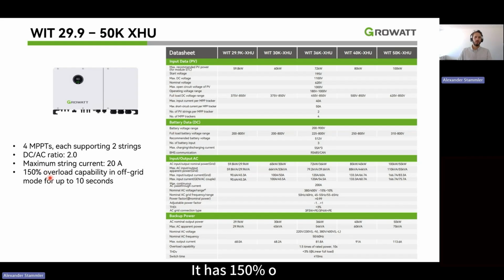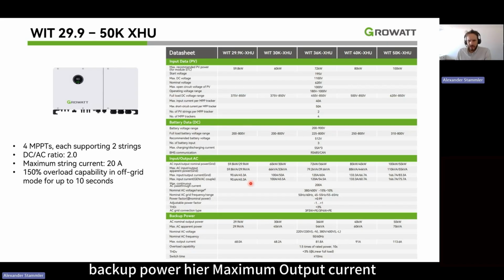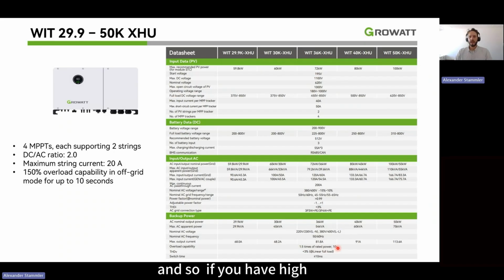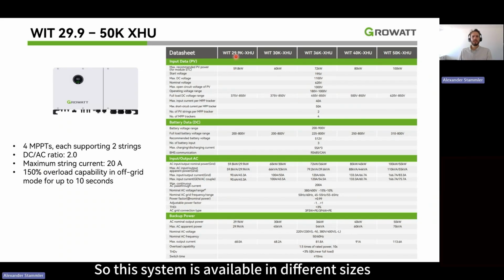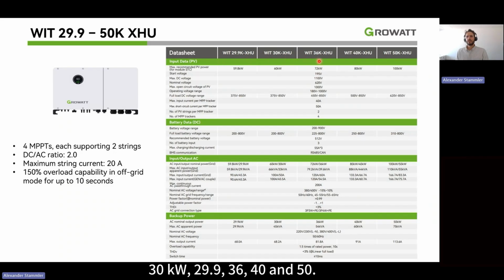It has 150% overload capacity in off-grid mode, meaning, for example, here, the 29.9 kilowatt AC output inverter can backup power, maximum output current, here, 1.5 times of the rated power for 10 seconds. So if you have high consumption for starting certain motors or so, this one will be able to deliver 150% overload capacity. Exactly. So this system is available in different sizes: 30 kilowatt, 29.9, 36, 40, and 50.